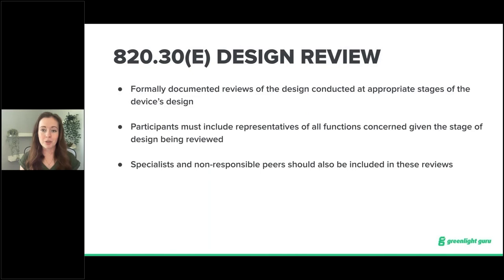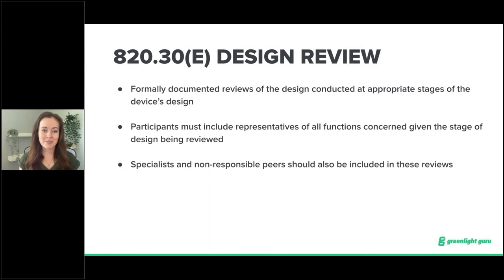How do design reviews actually take place? Most formal design reviews take the form of a meeting. In simple cases, the technical assessor and reviewer may be the same person. Even in simple reviews in a manager's office, you still need to document meeting minutes and action items. For more elaborate reviews, detailed written procedures are desirable to ensure all pertinent topics are discussed, conclusions are accurately recorded, and action items are documented and tracked. Design reviews ultimately come down to documenting and reviewing those documents appropriately, including meeting minutes, action items, and all individuals involved.